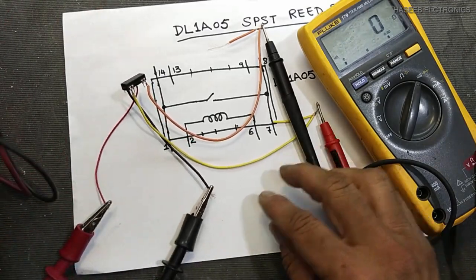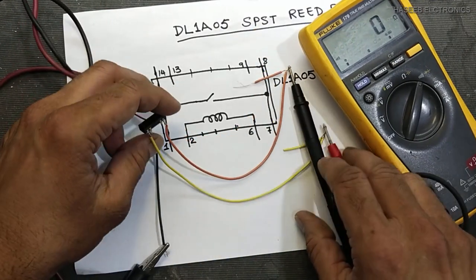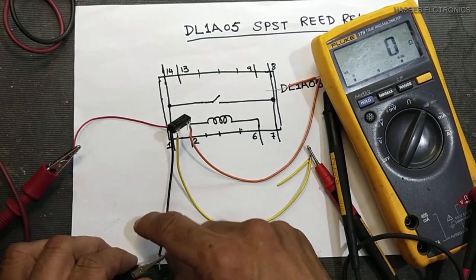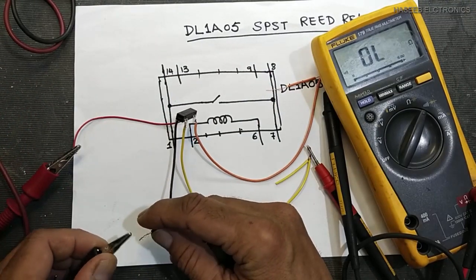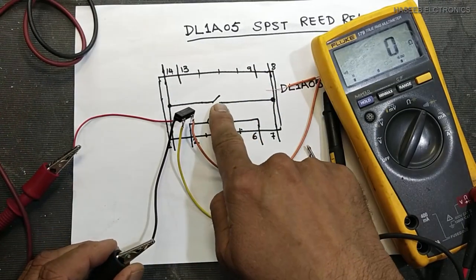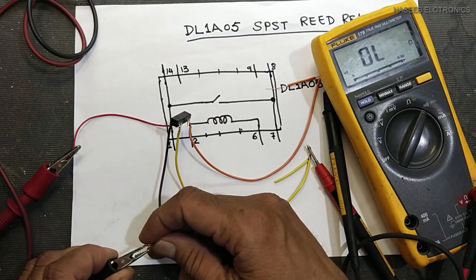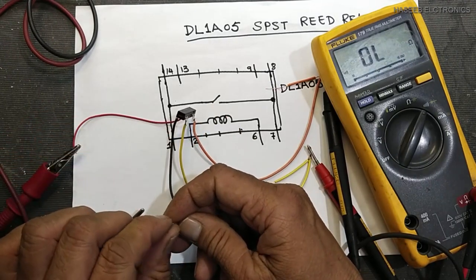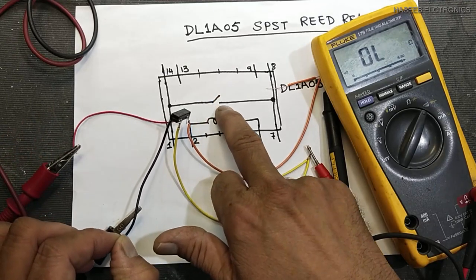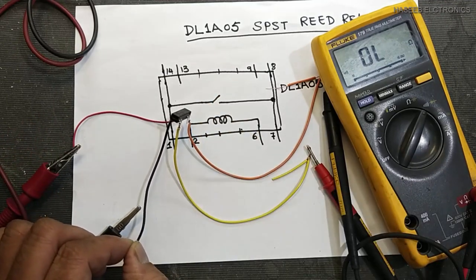This is the total testing. If it is making connection, that means this relay is good. If I remove this signal, this internal switch must open. Sometimes without this positive 5 volts, this switch is internally short circuit. It is permanently closed.